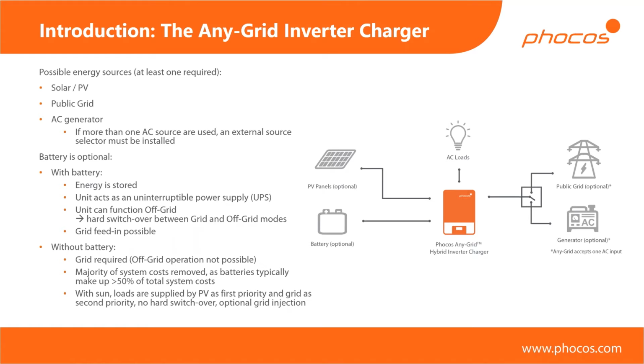But of course, because now we have absolutely no buffer in the system, and we have no fallback energy source if we don't have a grid connection, for example, then as soon as the PV power drops below the power of your loads, the inverter can only turn off. So this is not recommended. That's why we write that a grid is required. But technically speaking, it would work without a battery, even without an AC source.